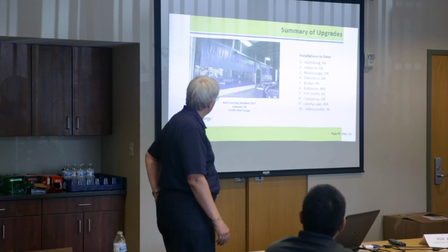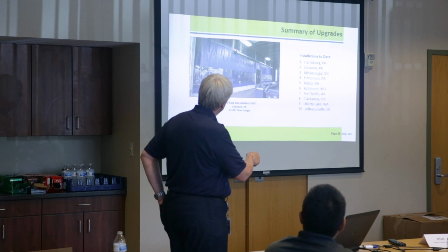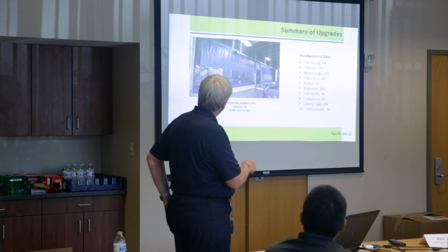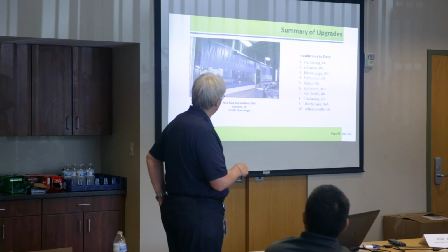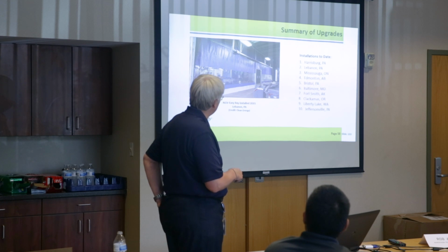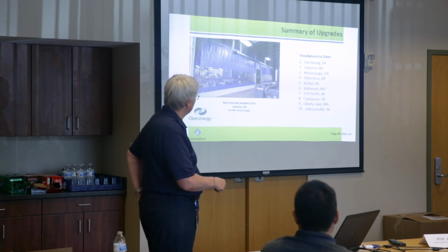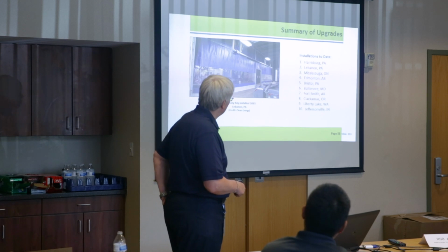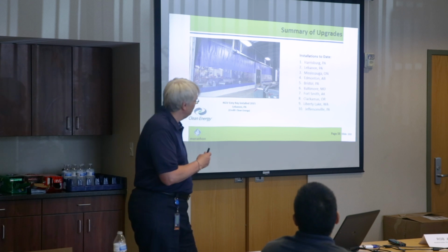You can see here there is a unit heater, a radiant tube heater here. I'm frankly not sure whether we're inside or outside of the space in this picture. But anyway, there is a radiant tube heater. If it's inside, that would have to be a low temperature heater. They gave me 10 installations to date. You can see these are pretty much all cold weather installations. Some of them very cold. We got Edmonton, Alberta there.